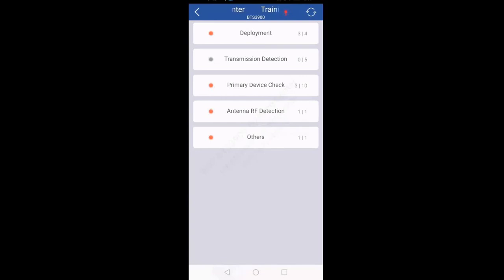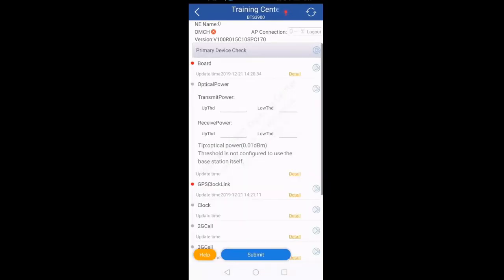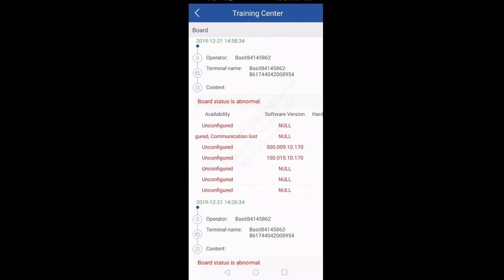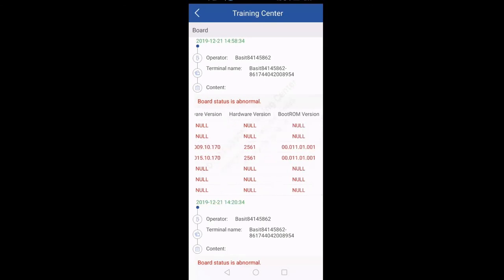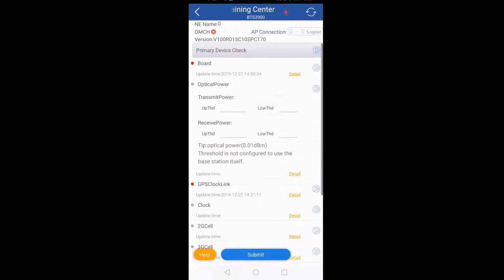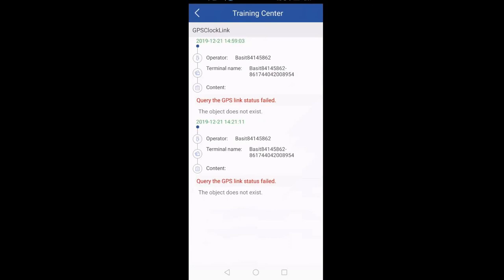If you want to check boards, go to the third option: Primary Device Check. The first option is Board — click the play button in front of Board. By clicking on Detail it will give you the details of all boards and their operational status, including serial numbers, whether the board is available, software version, hardware version, and boot ROM version. If you want to check GPS clock link, click on GPS Clock Link and click the play button — it will give you the GPS clock link. Currently there is no GPS connected here so the GPS link status has failed, but on site it will give you the GPS clock link as well.